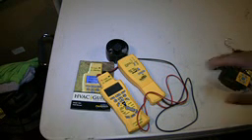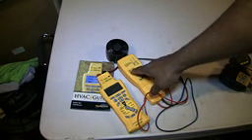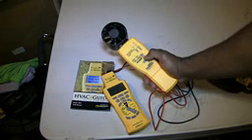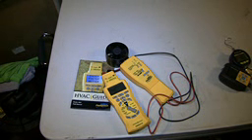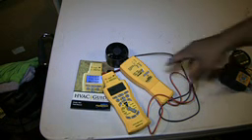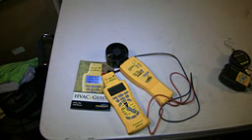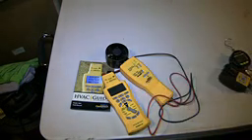Okay. Now, the only drawback to that, if you can call it a drawback, whenever you're using the AAV3 anemometer head, when it comes to calculating your CFMs and what have you, you can only leave the selection dial on one setting at a time. Okay, so unlike, let's say, the Testo 435, where you can measure the CFMs, the velocity and temperature and see all the information all at once, unfortunately with this HVAC guide, you can't do that yet.